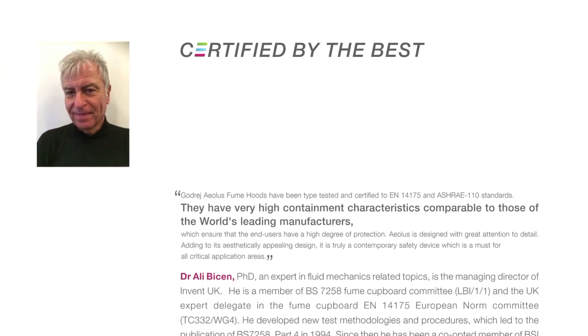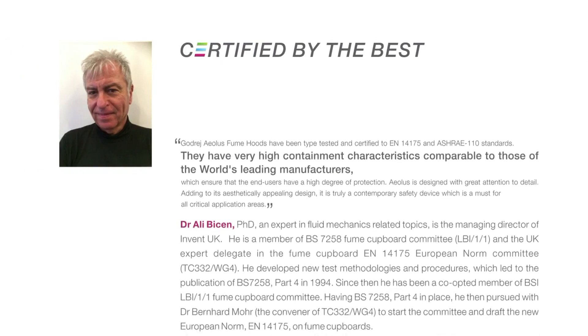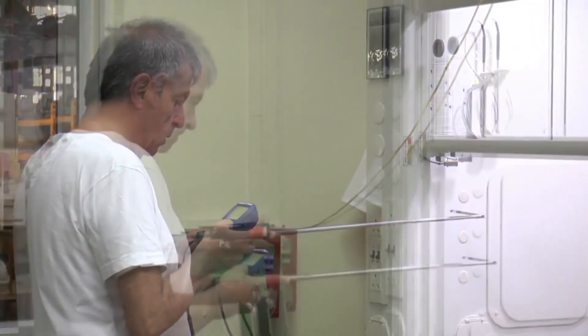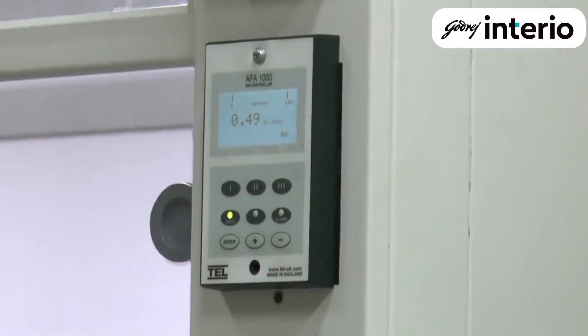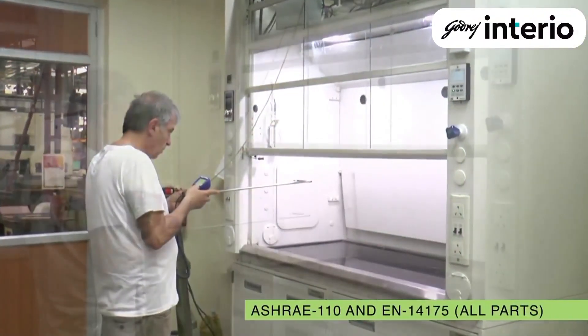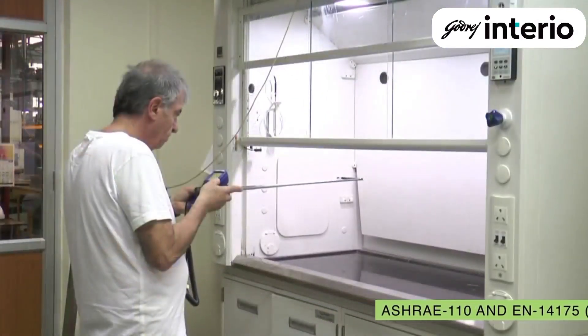Dr. Ali Bicen, the airflow expert from Invent UK and a veteran in the field of fume hood design and testing, says that Aeolus has very high containment characteristics comparable to those of the world's leading manufacturers. Aeolus is also probably the only fume hood to be compliant with both internationally accepted standards ASHRAE 110 and EN 14175, all parts.